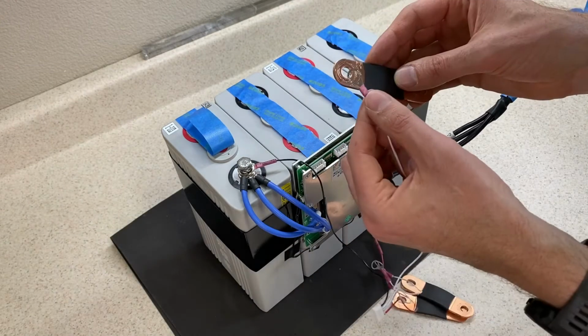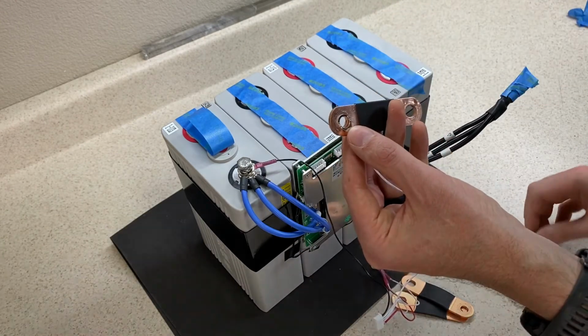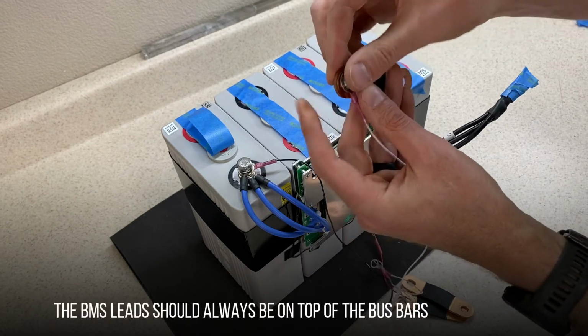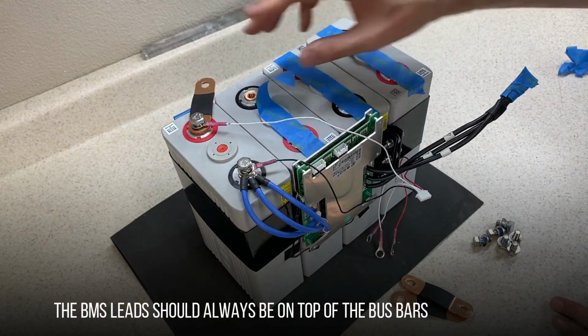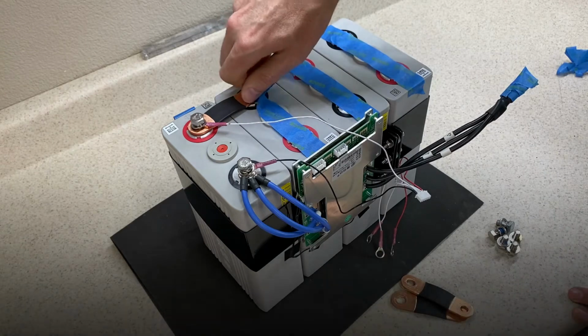Then lay your first white balance lead on one end of a bus bar, insert the bolt, and then thread it into the cell 1 positive terminal. Thread a second bolt into the other end of the bus bar to make sure that that bus bar can't accidentally rotate on us.